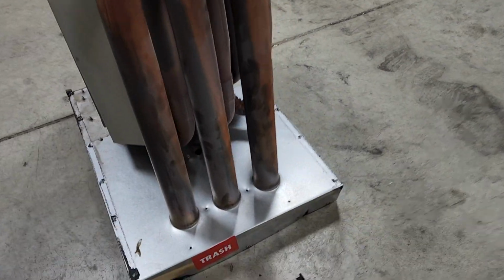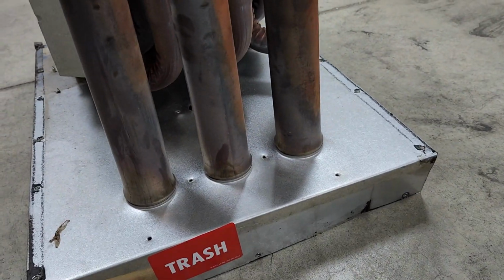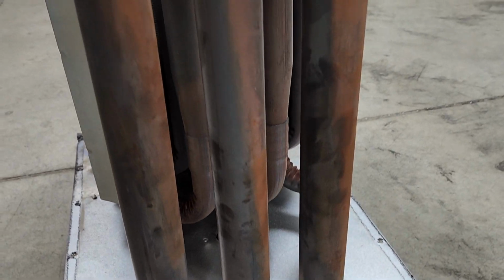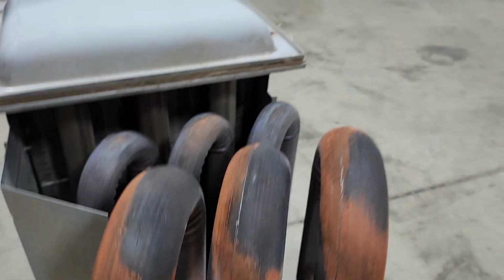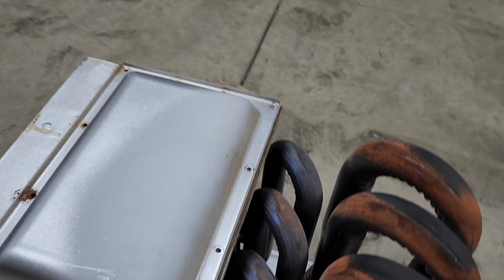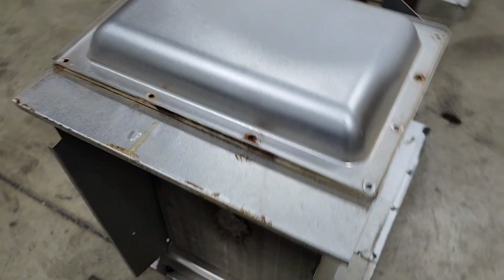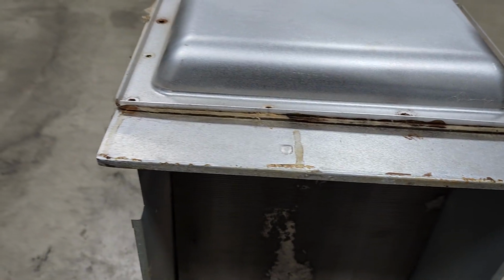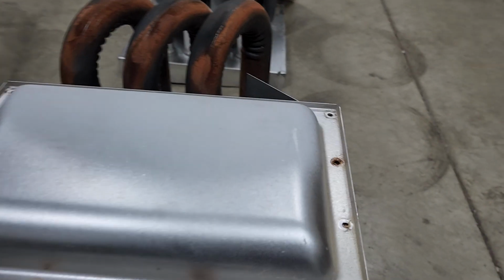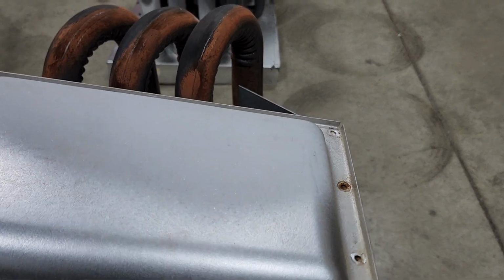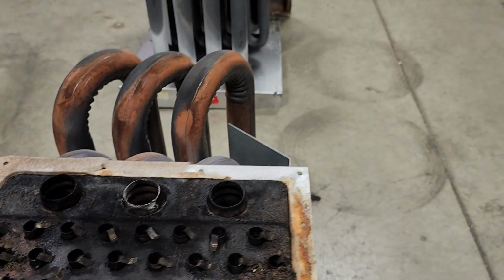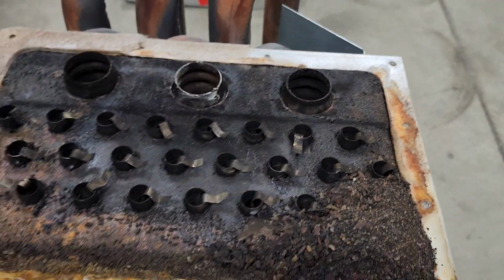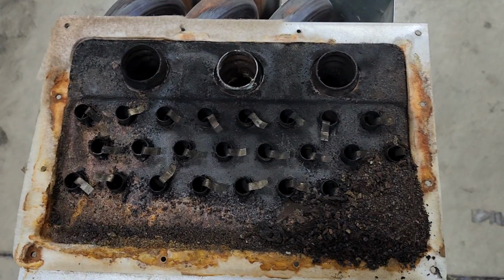Here's another example of a heat exchanger that looks like from day one it was overfired. The technician probably did not set the gas pressure appropriately during install. Also, again, it looks like this system short cycled. You can see condensate starting to drip out of the recoup cover. We shouldn't be condensing back there. Condensing should be happening in the secondary heat exchanger tubes only, and then making its way out of the drain.